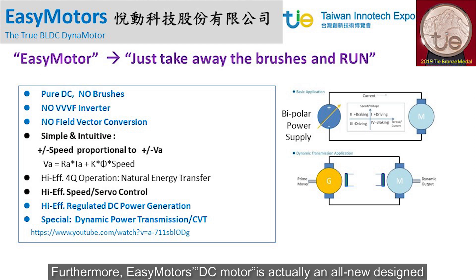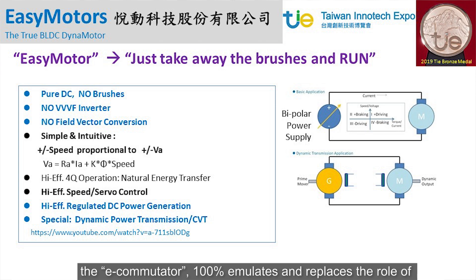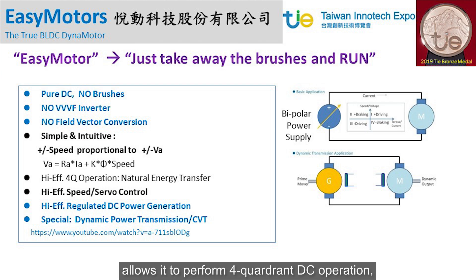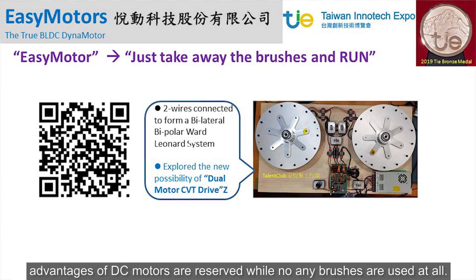Furthermore, the EasyMotors DC motor is an all-new designed brushless DC dyna motor, without the use of a VVVF inverter or complex FOC on the market. Instead, with our worldwide patented new power electronic design, the E-commutator 100% emulates and replaces the role of a mechanical commutator of a conventional DC brushed motor, allowing it to perform four-quadrant DC operation — the so-called Ward-Leonard system operation. Therefore, the intuitive, simple model and easy-to-use advantages of DC motors are preserved, while no brushes are used at all.